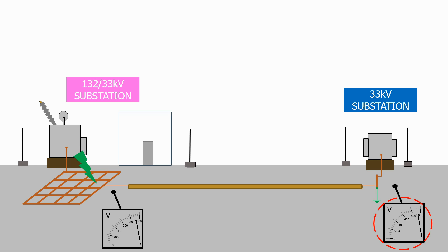The problem is that this grounding grid will not be designed to carry such a high voltage level, and anyone standing inside the 33kV substation or touching the metal enclosures of the equipment will be in extreme danger due to the touch and step potentials.